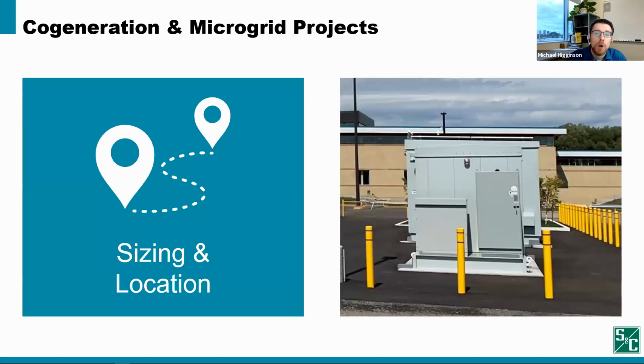Two of the most important considerations in the interconnection process are sizing and location: the size in megawatts of the resources interconnected, and where these new resources are going to go. It's common that the resources used on these projects are multiple megawatts, sometimes even over 10 megawatts. With large generators and energy storage systems of this size, their impact to the local power system can be significant, for example impacting short circuit levels locally as well as power flows on the local circuits. The physical size of these resources can also be quite large, so we have to find an appropriate and safe place to locate them on the project site.